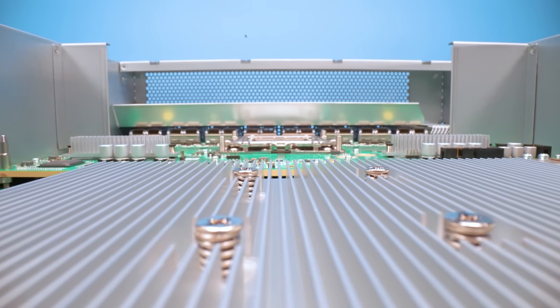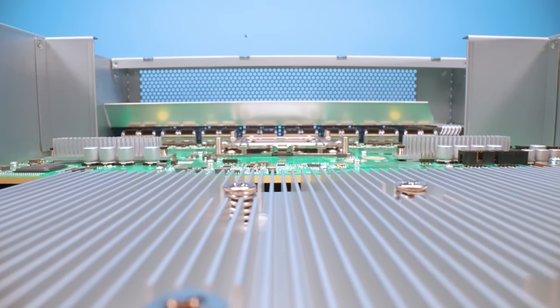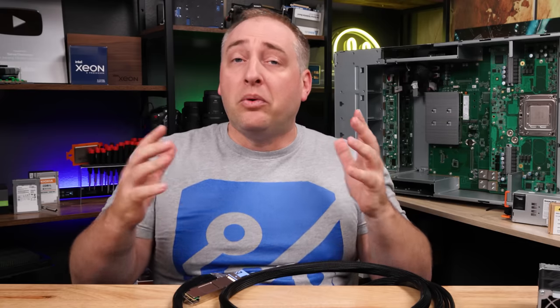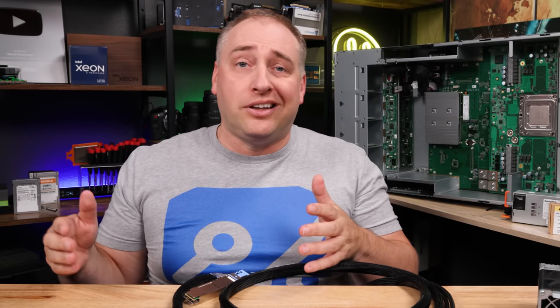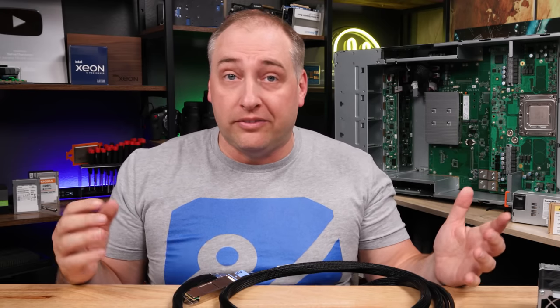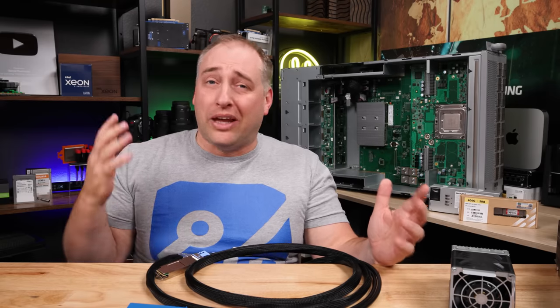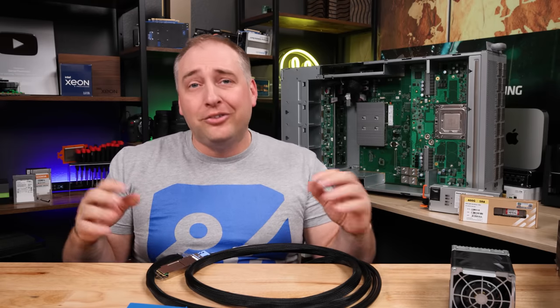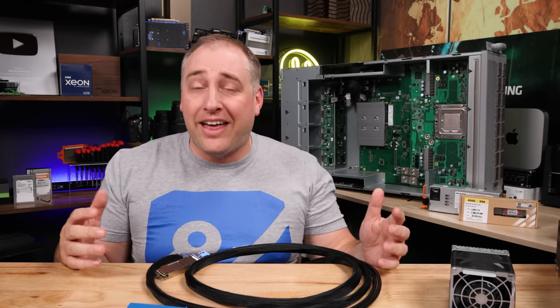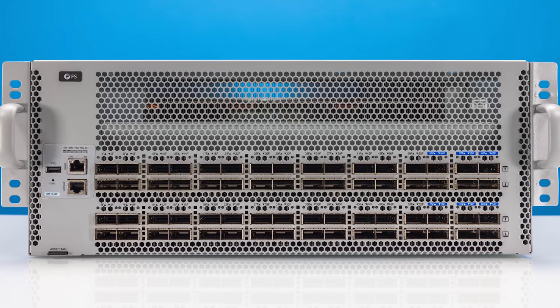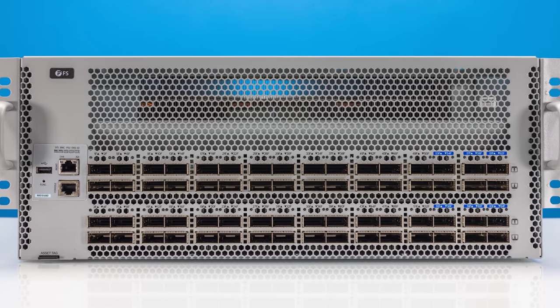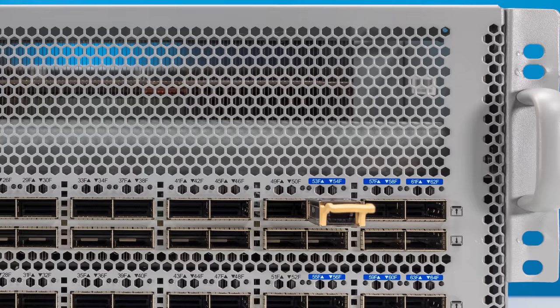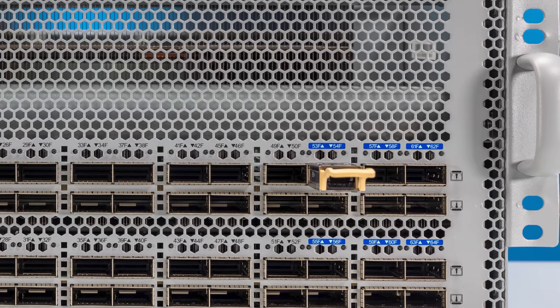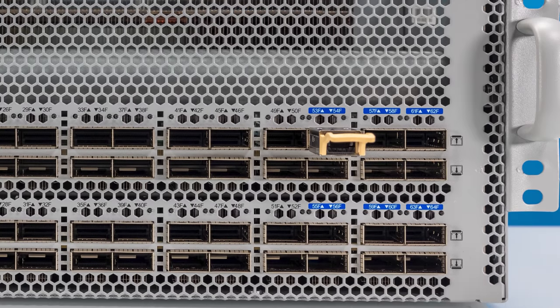Now, in front of the switch chip, what you're gonna see is that array of QSFP-DD cages. One of the big challenges with 400 gig networking is just cooling. The specs for these modules are up to 12, and depending on what kind you're using, up to 15 watts. When you have 64 of those things, you're generating around a kilowatt or so of just optical module power consumption, and that takes a lot to cool.